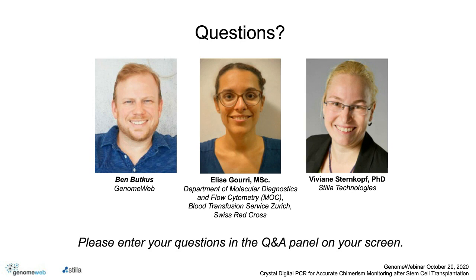The next question is for Stilla: do you have other consumable types apart from the Opal chip? Yes — we also have a second type of chip called the Sapphire chip. With the Sapphire chip, you can run a droplet volume of up to 30,000 droplets on a 25 microliter reaction, and can run up to four samples in one chip.